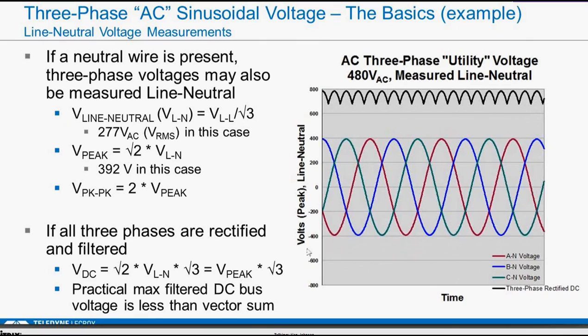So if you rectify all three phases, which would be rectifying a line-to-neutral signal, then the DC value would be calculated as here. So square root of 2 times the line-to-neutral times the square root of 3, because you have three different phases here that are adding vectorially. And so that is going to give you something just shy of 700 volts once it's filtered. This, of course, shows the addition of all these things, but not filtered. But you can see it would be about 679 volts DC when you're all done.